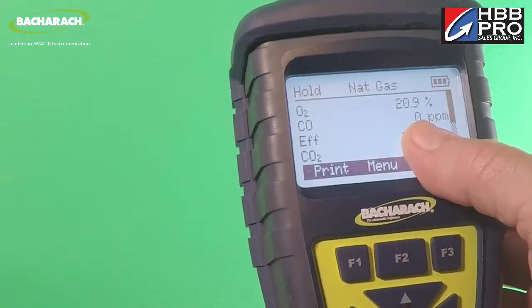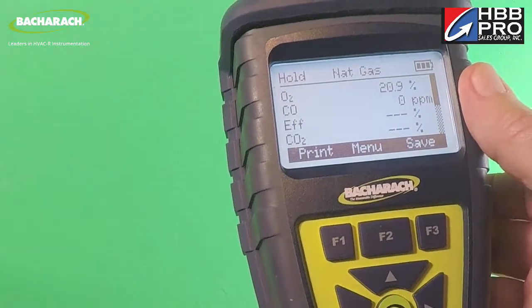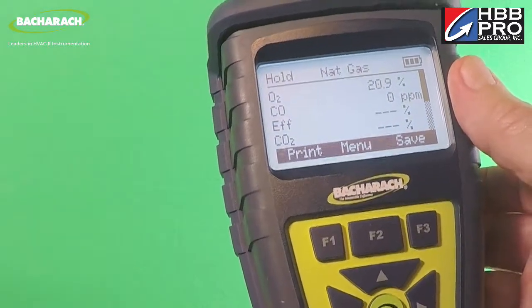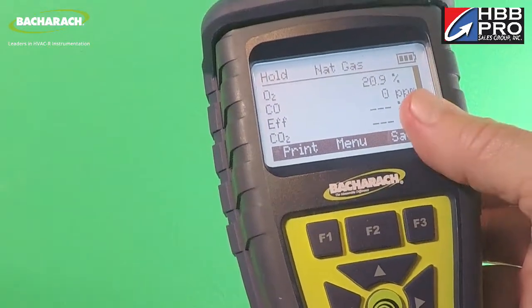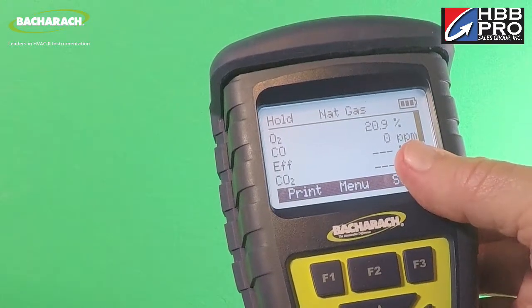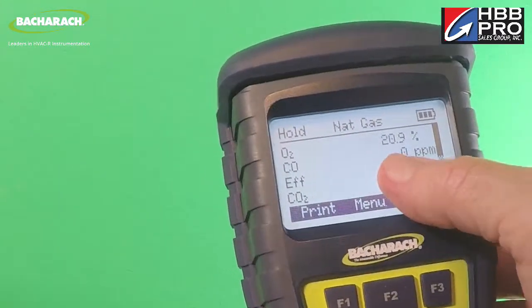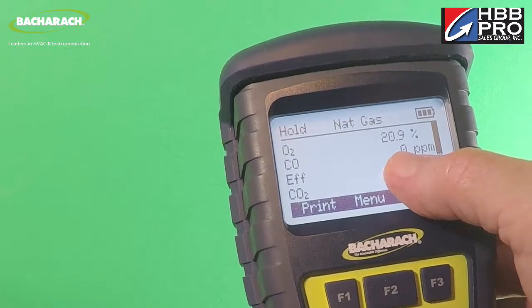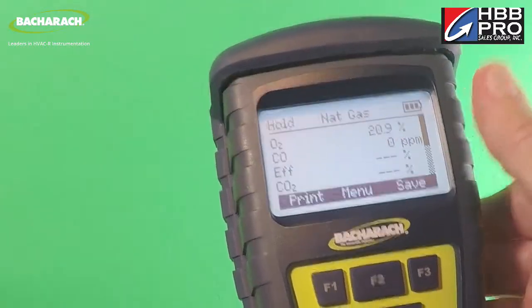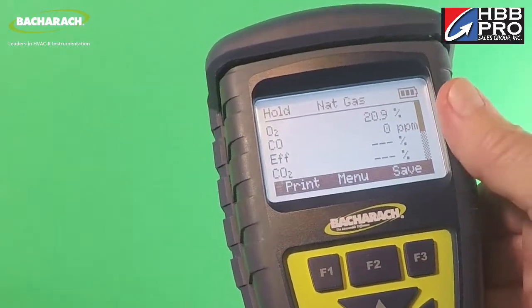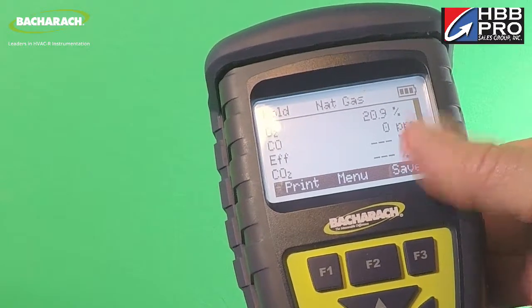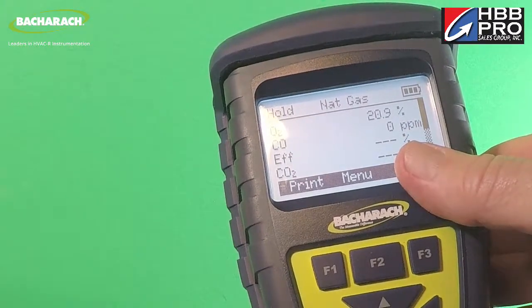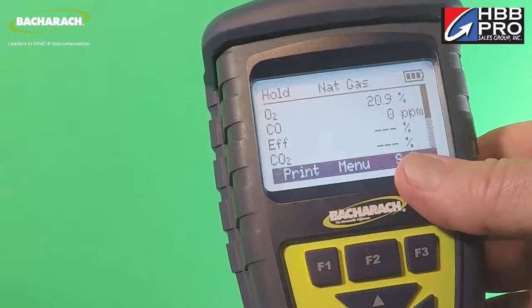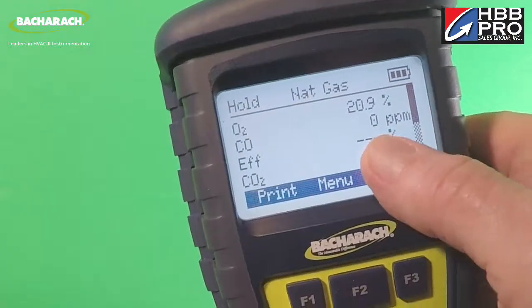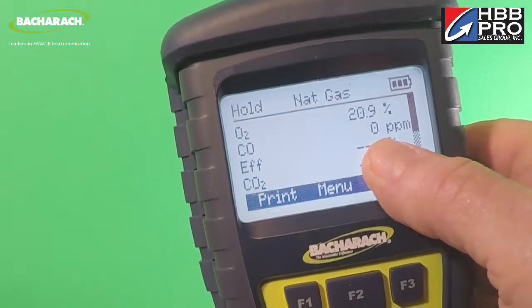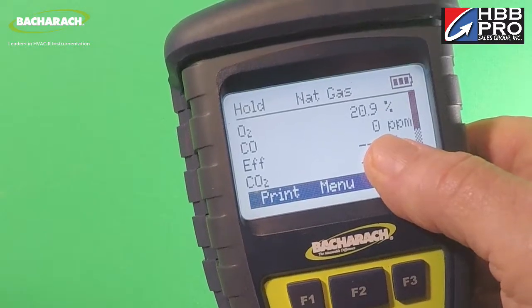Also keep in mind that if there are significant, substantial levels of CO in the space, the instrument will come up with a CO sensor error message when the countdown is complete, and the run screen will display just some asterisks and then ppm. If this ever happens, you need to immediately evacuate to clean air, turn the instrument off, then turn it back on again. If it powers up without that error message and comes to 0, like you see on the screen here, walk back into the space and see what's going on.